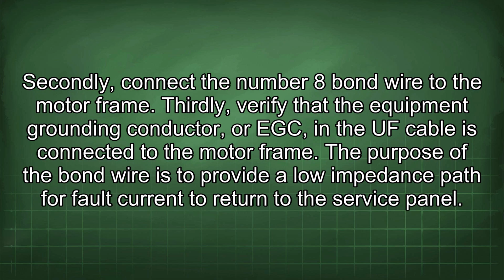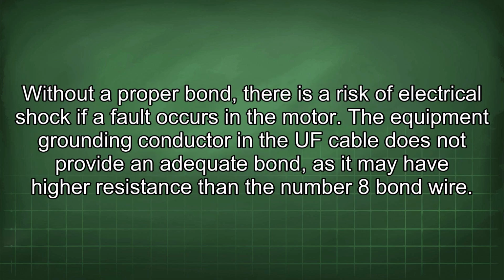The purpose of the bond wire is to provide a low impedance path for fault current to return to the service panel. Without a proper bond, there is a risk of electrical shock if a fault occurs in the motor. The equipment grounding conductor in the UF cable does not provide an adequate bond, as it may have higher resistance than the number 8 bond wire.